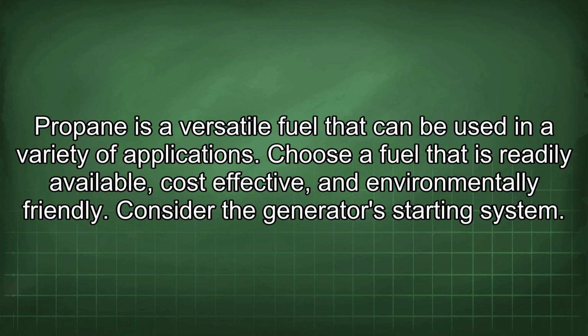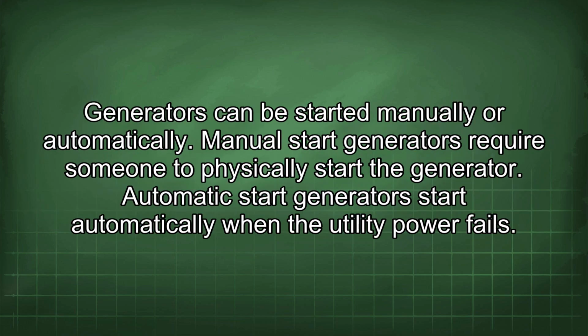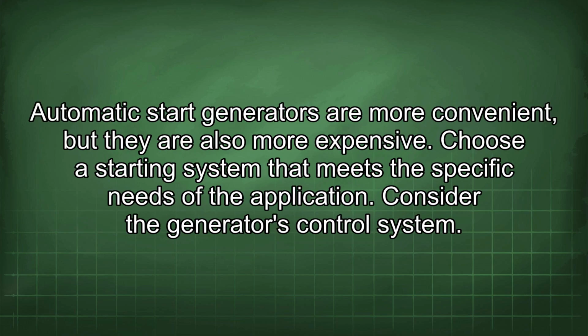Consider the generator's starting system. Generators can be started manually or automatically. Manual start generators require someone to physically start the generator. Automatic start generators start automatically when the utility power fails. Automatic start generators are more convenient, but they are also more expensive. Choose a starting system that meets the specific needs of the application.